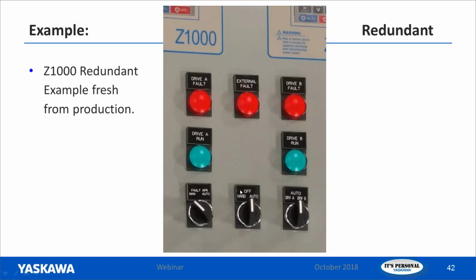Next we have our HOA switch, and of course that would be related to whichever drive may be running at the time. You have your full hand-off-auto control. Then over here we've got our drive A, drive B switch, so this gives you the ability to walk up to the unit and run it in drive A, or have drive B run, or just have it in the auto position so that your remote controls can be controlling the package.